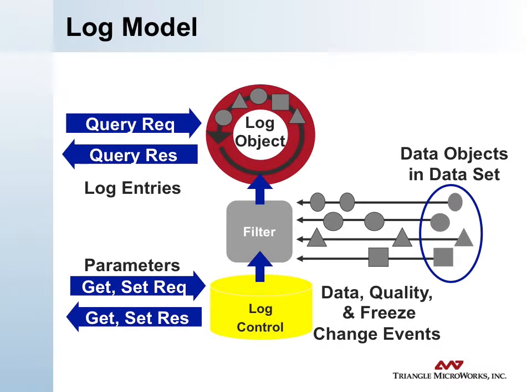This diagram shows the log model, and other than the size of the circular buffer, it's the same as the buffered report control model — except that instead of sending data on changes, the stream of data isn't actually sent to the client unless the client requests it. They can request it in multiple ways to retrieve the log entries, which correspond to the reports in the reporting model. There's a control block that controls this process, and the client can get or set the parameters to manage that.